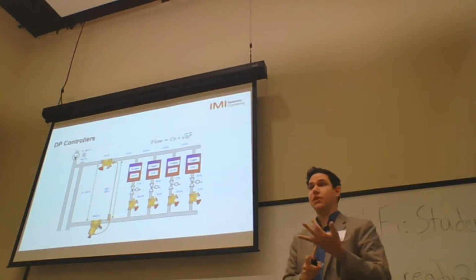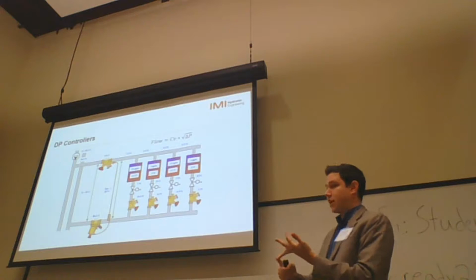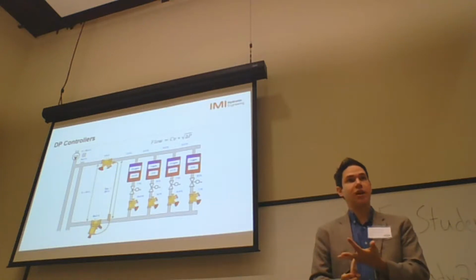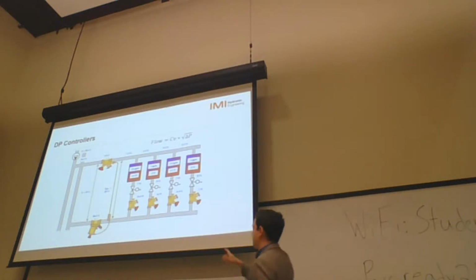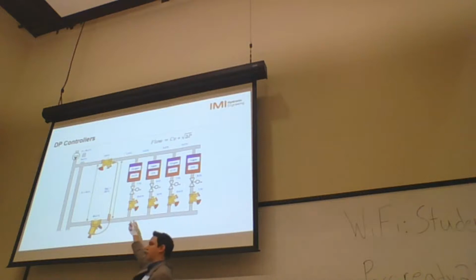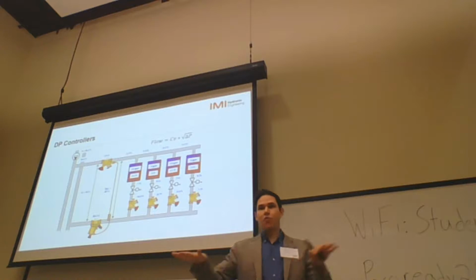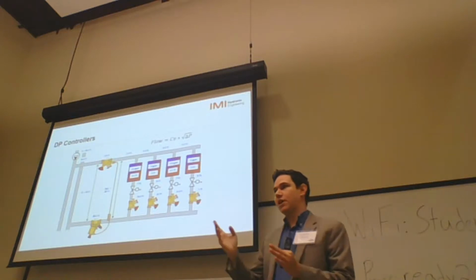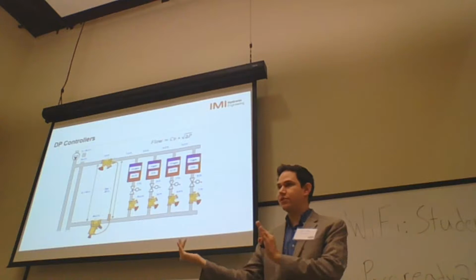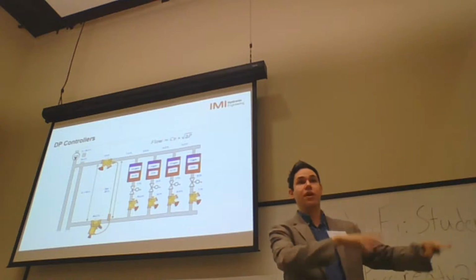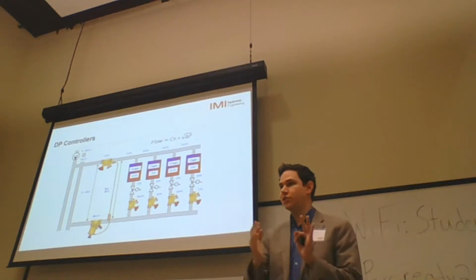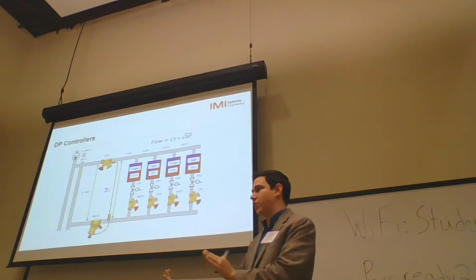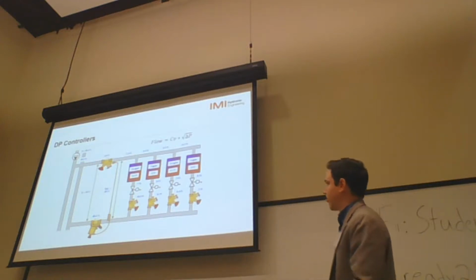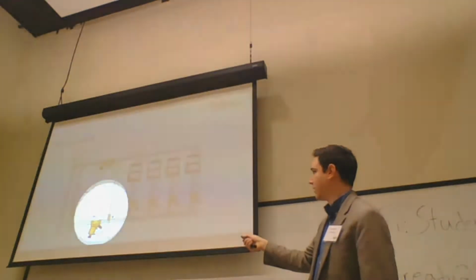So you're basically increasing the control valve authority, making the branch pressure independent, even if you have manual balancing valves on each coil. So if you have different wings, different floors, different risers, as soon as you're done with that riser, you can open, close, or do whatever you want in the rest of the installation. That branch specifically will not change the flow rates because it's keeping a stable differential pressure right there.